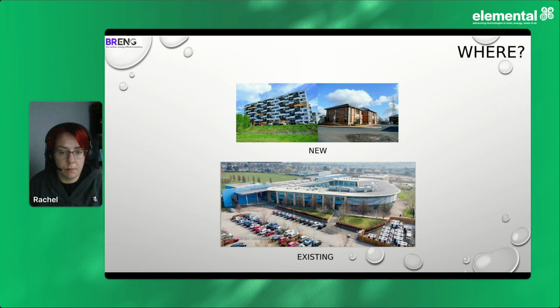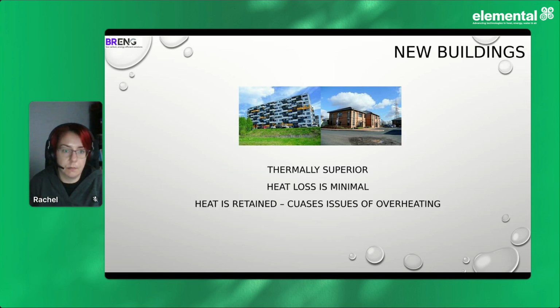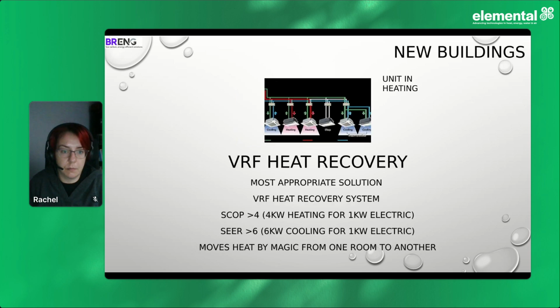So first we would look at is where are we going to heat? Is it a new building or is it an existing building? So new buildings, they're thermally superior. The heat loss is minimal and heat is retained. But because the heat is retained, that also causes issues of overheating. What we found in these type of environments, a VRF heat recovery system is your best option.